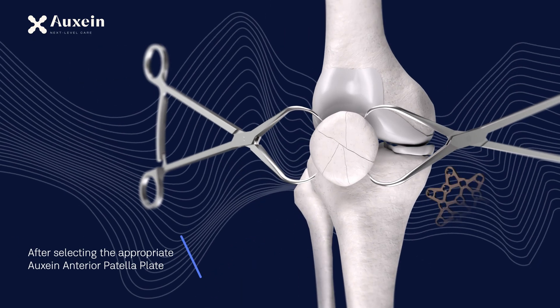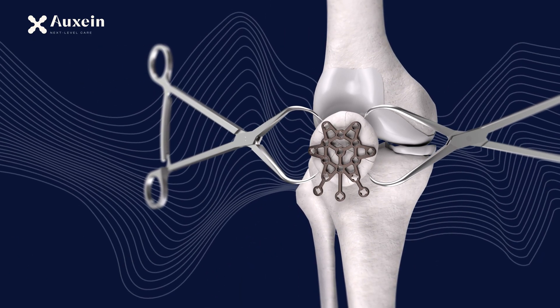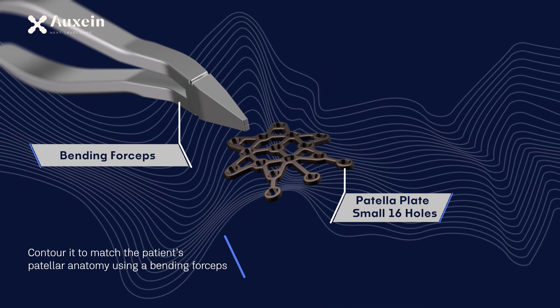After selecting the appropriate Auxein anterior patella plate, contour it to match the patient's patellar anatomy using a bending forceps.